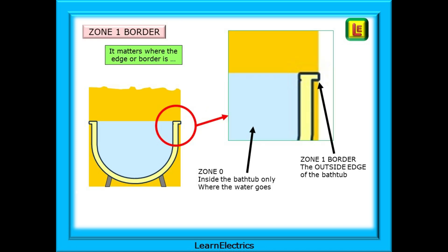We must understand the zone 1 border — it can cause confusion and often appears in exam questions as it's so easy to get wrong. Zone 0 is inside the bathtub, but zone 1 is measured to the outside edge of the bathtub. With most bathtubs that can be a difference of 50 millimeters or more.